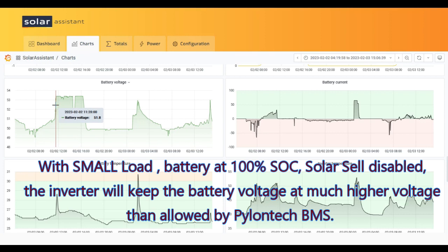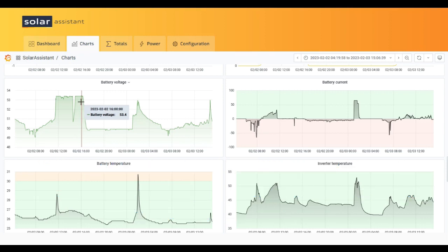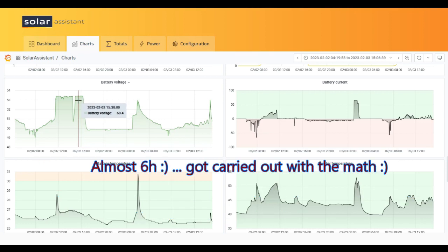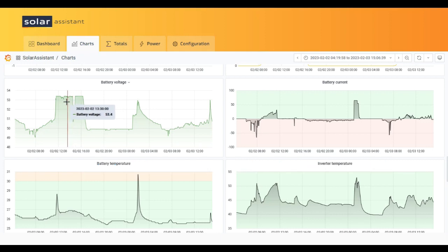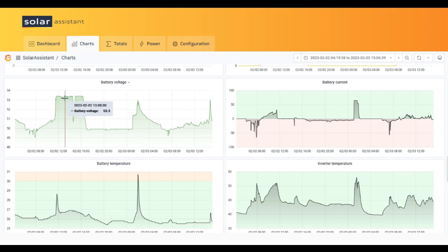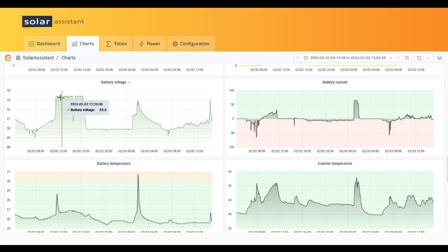You can see here the voltage will be kept from 11:30 until 16:00, so for four hours it will try to keep the voltage over because there is so much sun and there is no consumption, no load. This is an inverter that's remote from me at about 200 kilometers from here, so I could not just go and make changes locally. I've also seen voltages of 53.5 or even more.